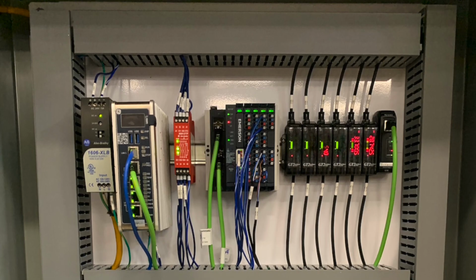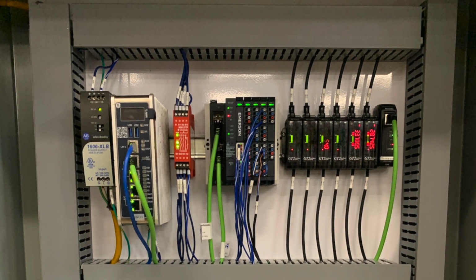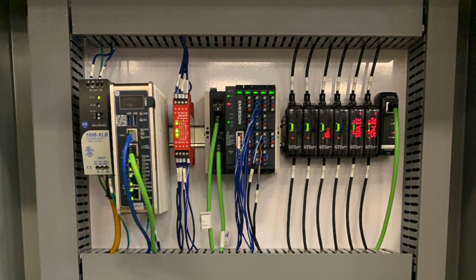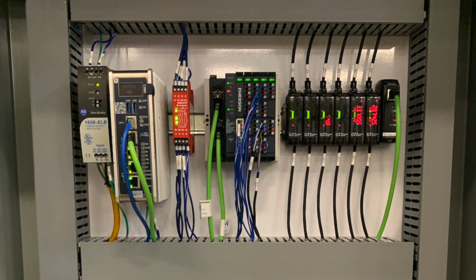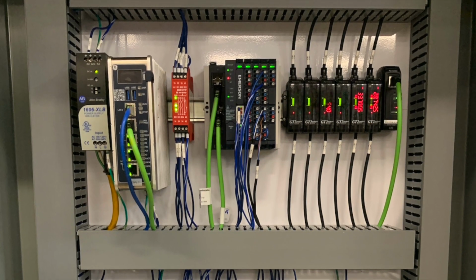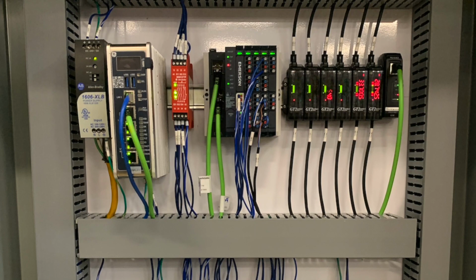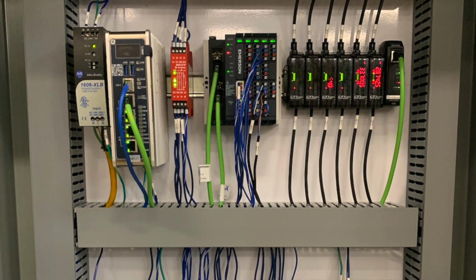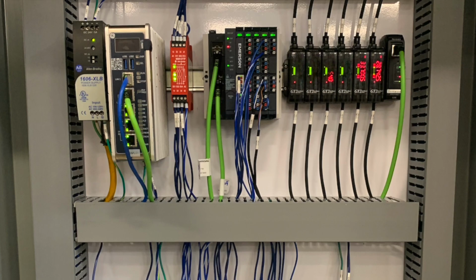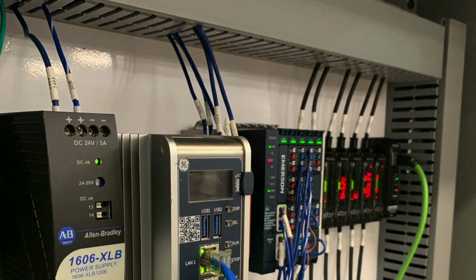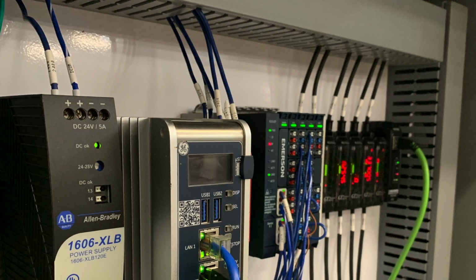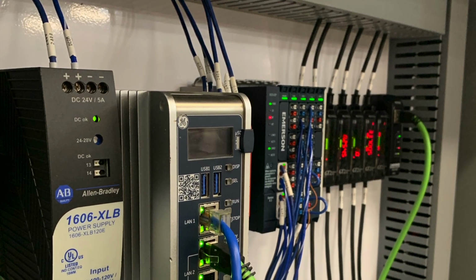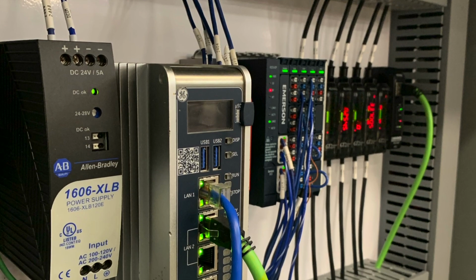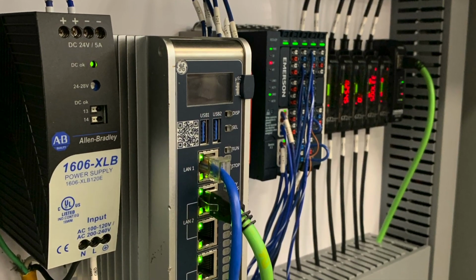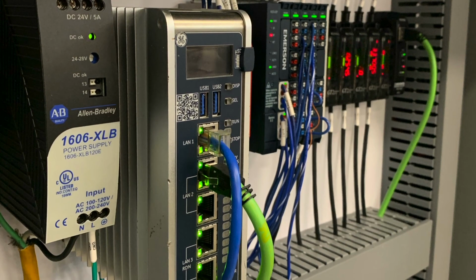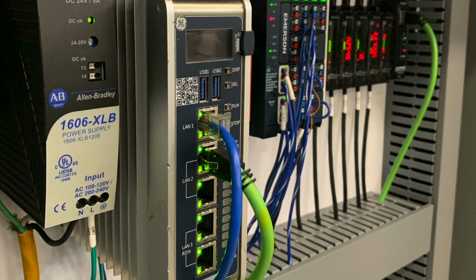To the right of the power supply is the PLC, which is the computer that runs the device. To the right of the PLC is the safety relay. This relay is connected to the e-stop on the HMI panel. When the e-stop is pressed, the safety relay cuts power to its contacts. This removes power from the pneumatic valve, retracting the LVDTs, and also breaks the circuit to the main line's safety relay network, stopping the entire roll forming line. This ensures our system is fully integrated into the existing manufacturing process as safe as possible.